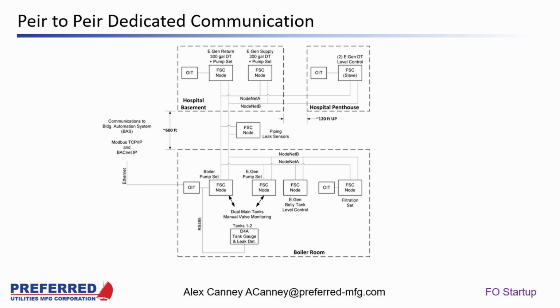The beautiful thing about the NodeNet communications and the FSC is that you're making it a modular system. You have a control package, say the pump set, that's your master panel or node 0, the one that handles all the stuff. Then you have individual nodes based upon, say, you have 3 day tanks, each with its own dedicated node number. The beauty is all 4 of those nodes are connected by 2 shielded cables, NodeNet A and NodeNet B, which handle the communications between the 4 different controllers.